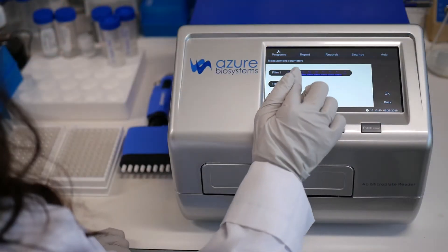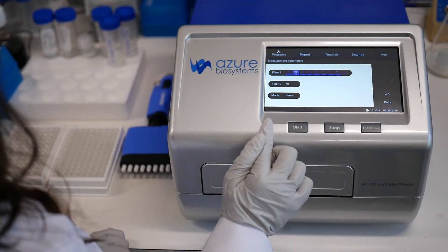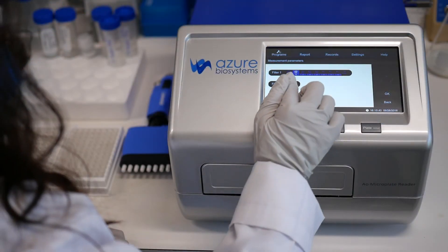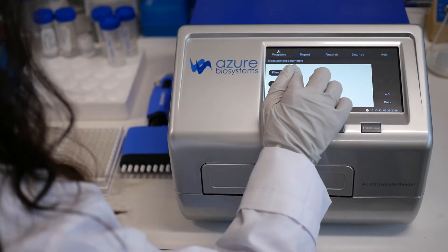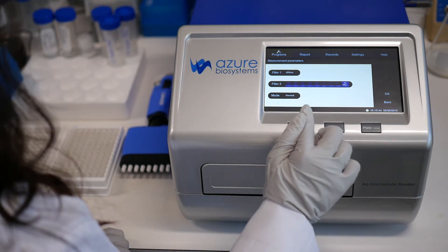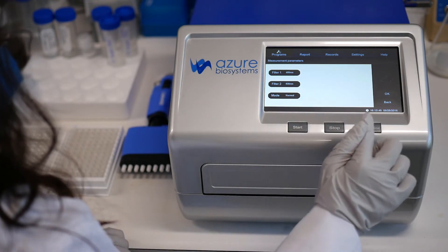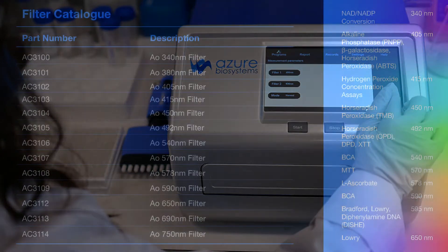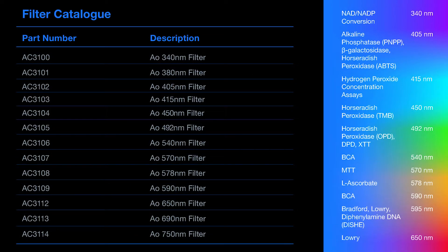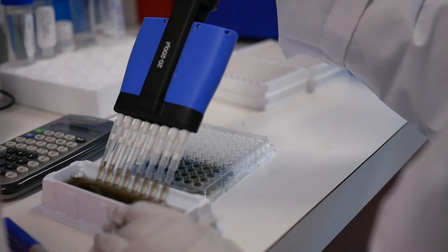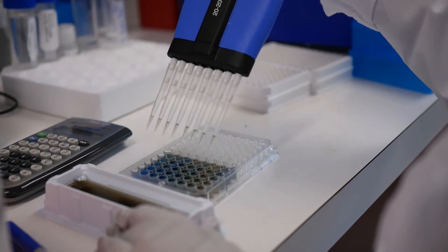With the ability to read up to two wavelengths at a time, each plate reader comes with an 8-position filter wheel equipped with 5 standard wavelengths and 3 custom wavelengths selected from Azure's wide selection of optional filters, assuring that you have the wavelength for your lab's assay needs.